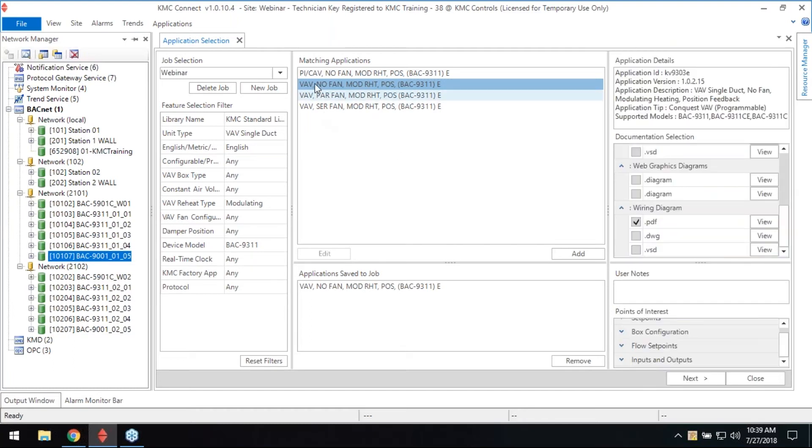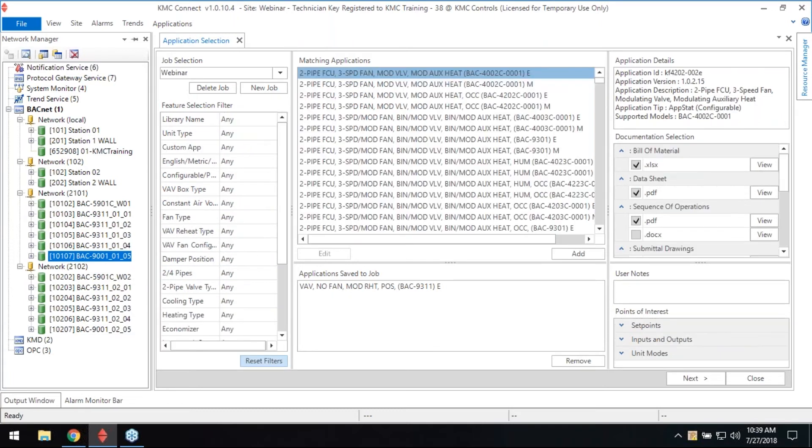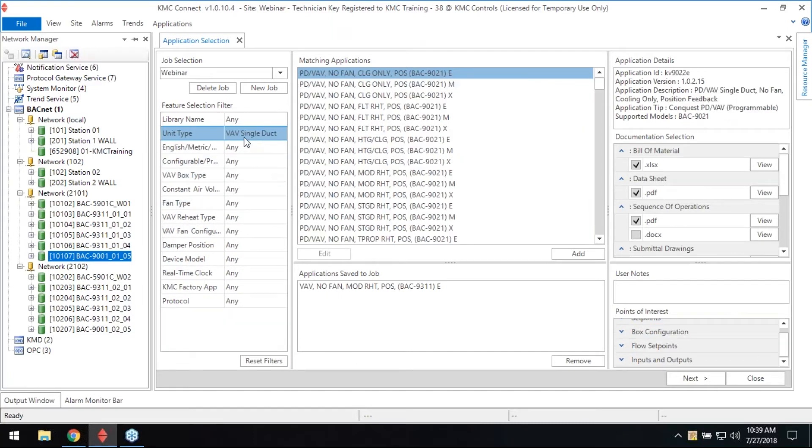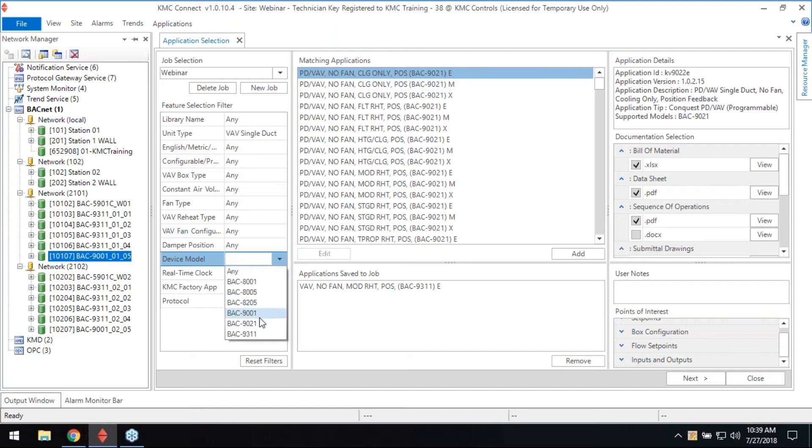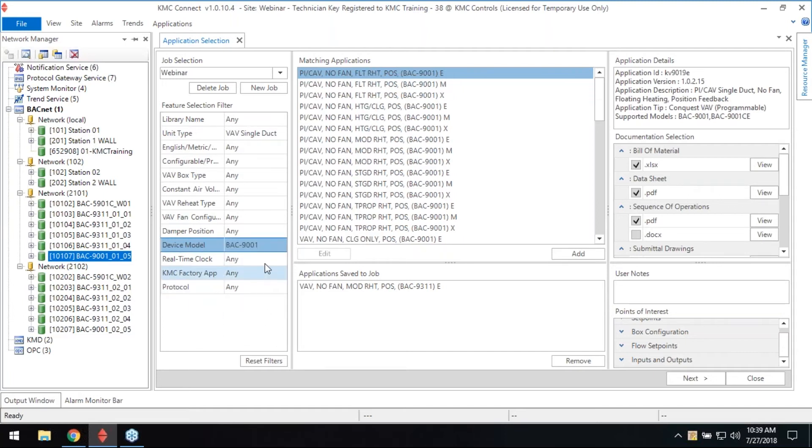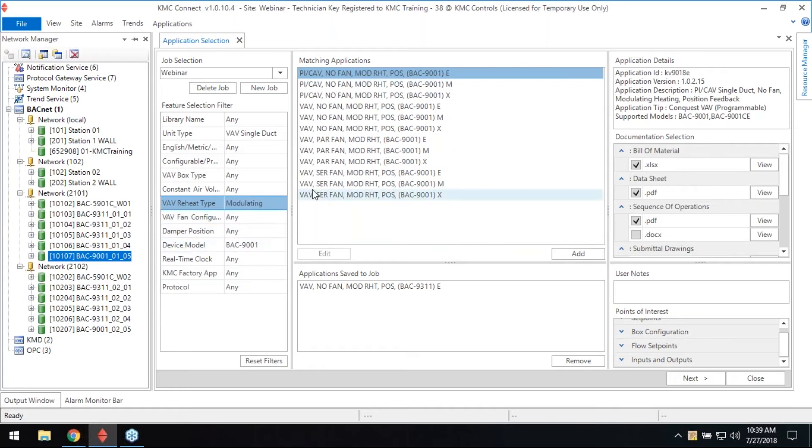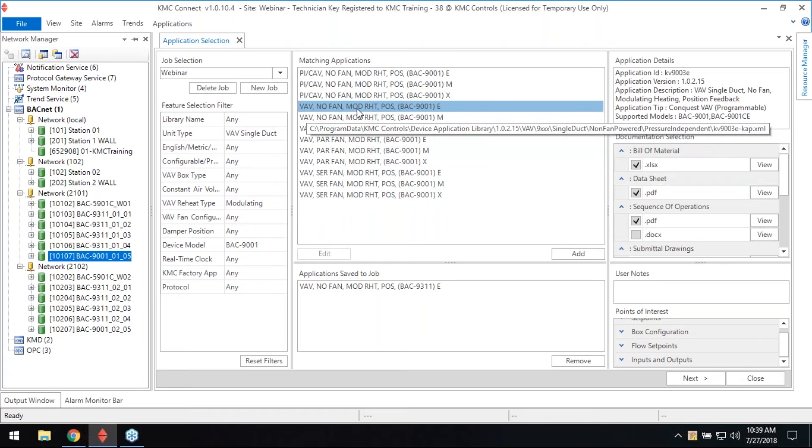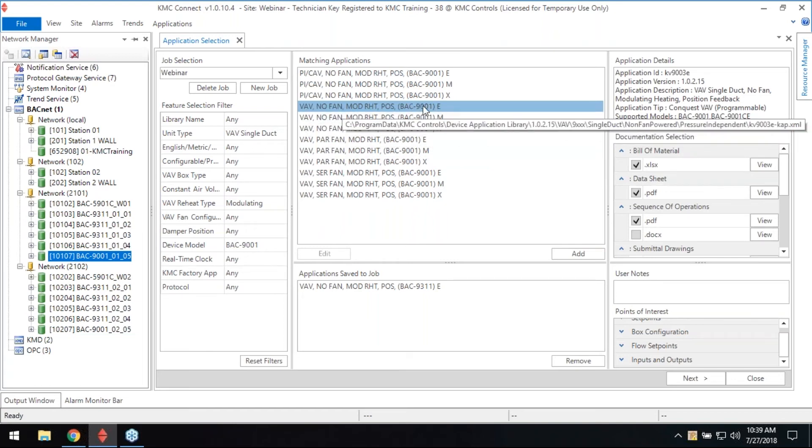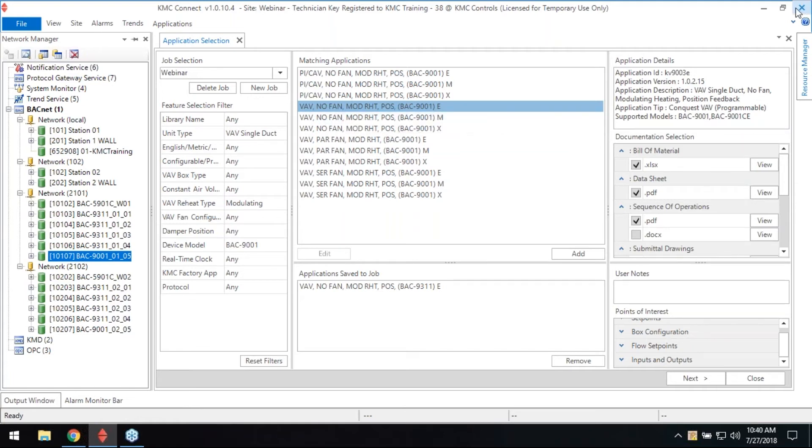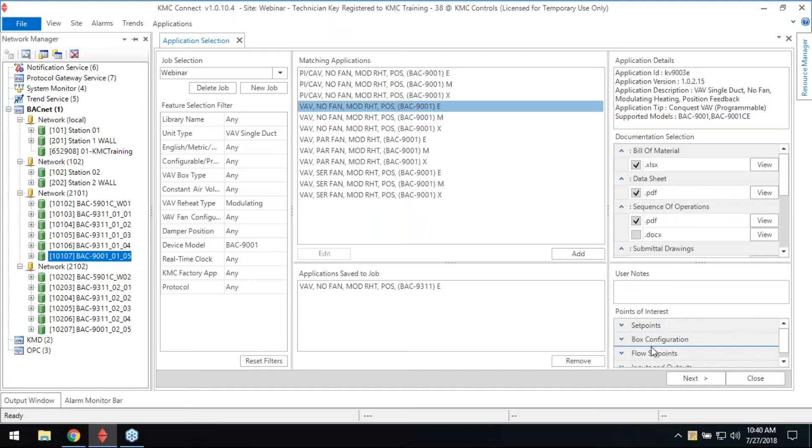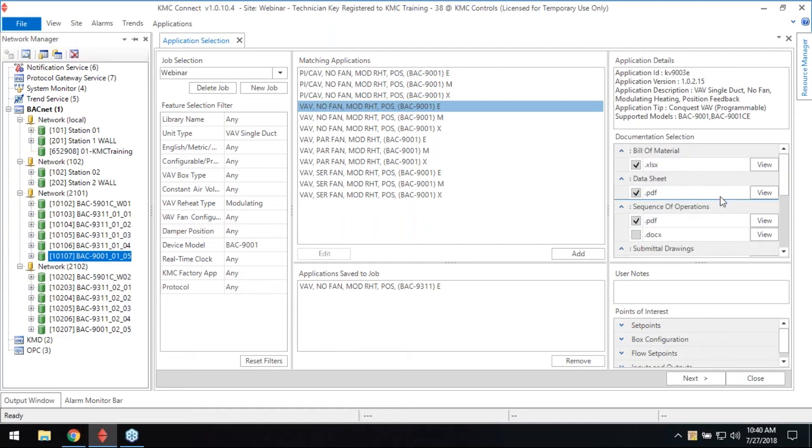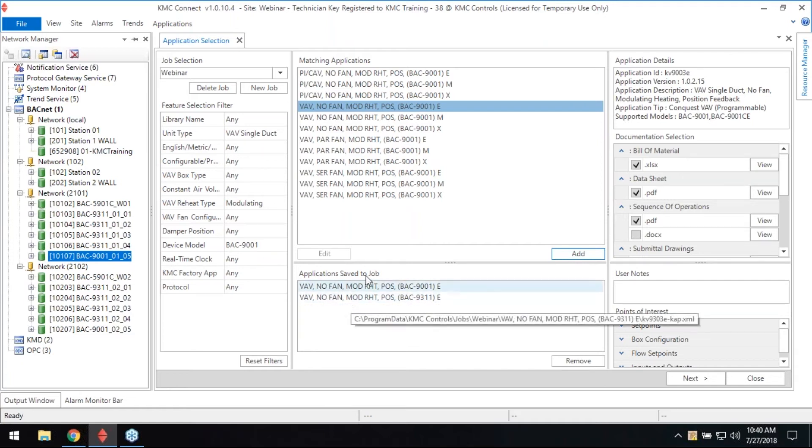So now we need to look at our other VAV, the 9001 VAV. I'm going to reset the filter down here. It's still a single duct, device model 9001. The reheat was modulating. VAV no fan modulating reheat position 9001. So it's a different model, it has the integrated actuator. It also has the documentation, points of interest that you may find on a graphic. All the same type documentation specific for this controller. So we're going to add that to our job also.